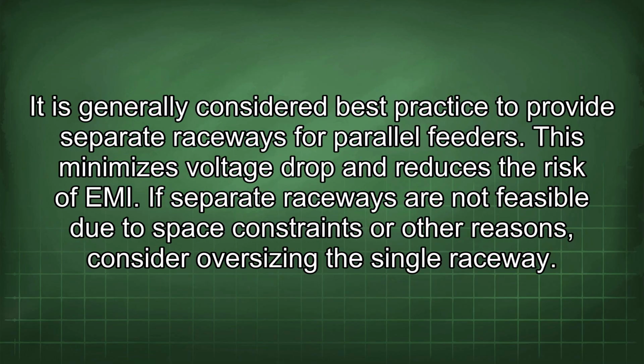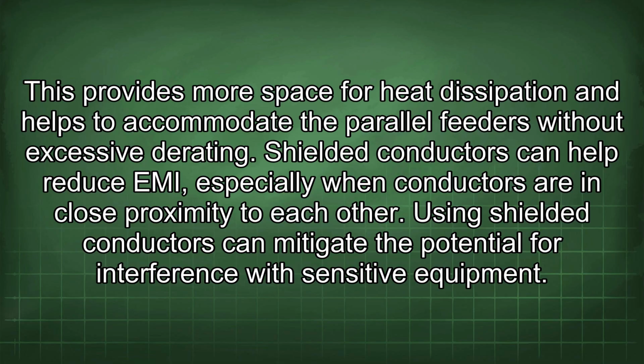It is generally considered best practice to provide separate raceways for parallel feeders. This minimizes voltage drop and reduces the risk of EMI. If separate raceways are not feasible due to space constraints or other reasons, consider oversizing the single raceway. This provides more space for heat dissipation and helps to accommodate the parallel feeders without excessive derating.